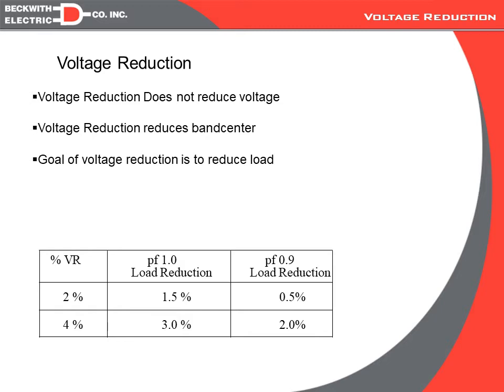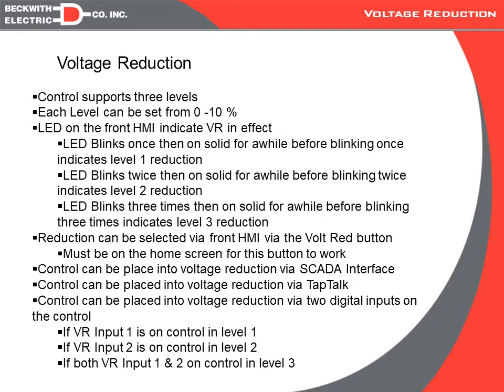And with that, there are multiple ways that we can institute voltage reduction on an M-6200A. First of all, we have three different programmable levels, level 1, level 2, and level 3. And each of these levels can be set for any percentage from 0 to 10%. There is an LED on the front of the M-6200A for voltage reduction, and it'll be off if we're not in reduction, and it'll be on if we are, but it'll blink, and the rate of blinking will determine which of the three levels. So for level 1, it'll be on solid, then blink once, then on solid, blink once. Level 2, it'll be on solid, then blink twice in a row, then solid. And level 3 would be solid, blink 3 times in a row, and then solid.